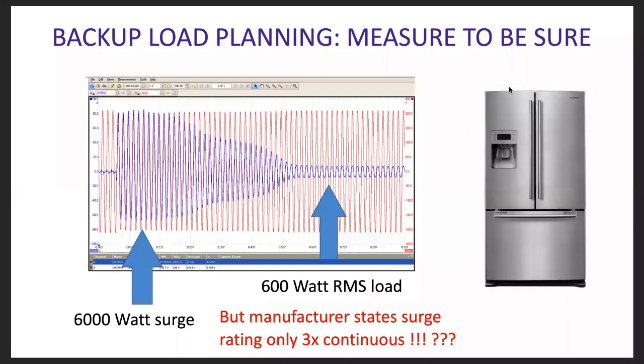Quick example of what you might see during backup load planning, or actually what you could see if you had a field O-scope. But I think the point of this slide is to show that although the manufacturer's nameplate may show that its surge rating is 3 times continuous, it can, depending on serviceability of the equipment, how old it is, et cetera, actually surge quite a bit higher. So measuring the loads is ultimately important, even more important than jotting down manufacturer nameplate ratings.